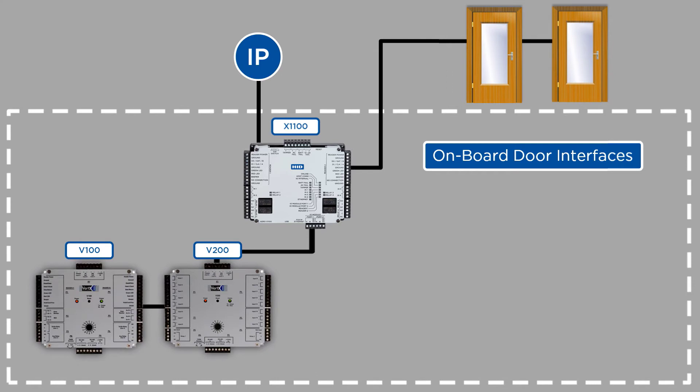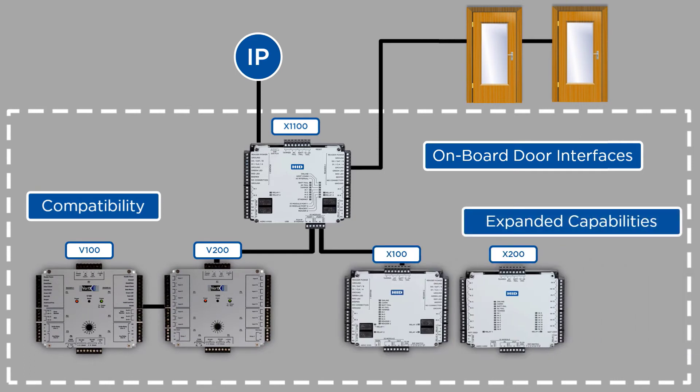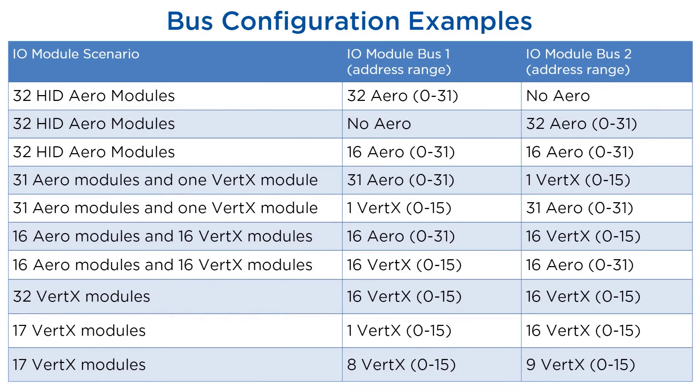With the X1100 installed you can continue using the V100, V200 or V300 modules that you have attached, but also begin adding X100, X200 or X300 Aero modules on the second communications bus. The Aero X1100 is able to support a number of bus configurations in order to facilitate existing VertX installations as well as those running both Aero and VertX, for example during a migration process. As you can see from this table, there are a number of ways to do this, but it is important to ensure your specific needs are met by these capabilities.